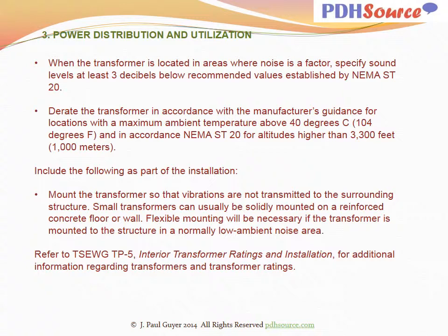Derate the transformer in accordance with the manufacturer's guidance for locations with a maximum ambient temperature above 40 degrees centigrade, 104 degrees Fahrenheit, and in accordance with NEMA ST20 for altitudes higher than 3,300 feet, 1,000 meters. Include the following as part of the installation. Mount the transformer so that vibrations are not transmitted to the surrounding structure. Small transformers can usually be solidly mounted on a reinforced concrete floor or wall. Flexible mounting will be necessary if the transformer is mounted to the structure in a normally low ambient noise area. Refer to TSEWG TP5 Interior Transformer Ratings and Installation for additional information regarding transformers and transformer ratings.